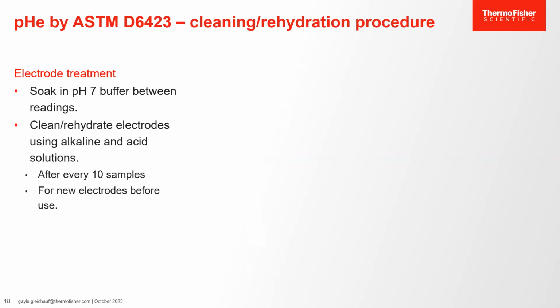Following the ASTM PHE method, the electrode is soaked in water-based pH 7 buffer between readings to prepare it for the next sample. This rehydrates the glass electrode, a necessary step to preserve the electrode's response characteristics. The electrodes are cleaned and rehydrated at least every 10 samples by alternately soaking in acid, then alkaline, then acid solution for about 30 seconds each. New electrodes are treated by this procedure before the very first use.